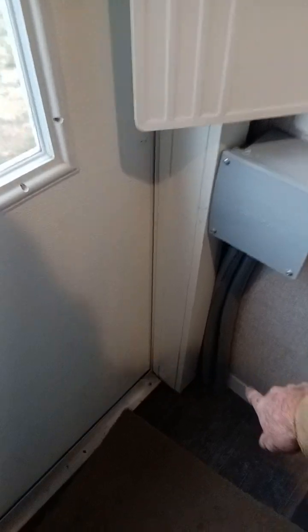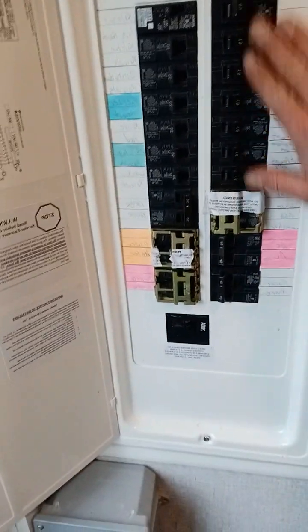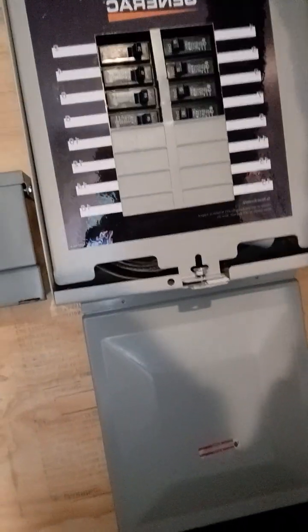The neutrals are bonded on the actual leg itself, and ground is on a separate ground from the actual house itself. That's where all the wiring is coming up through the box here, going into the wall and into our panels. We ran the transfer switch and seal tight underneath, coming up into here for outgoing power — which is inverter one and two for L1 and L2 power output.